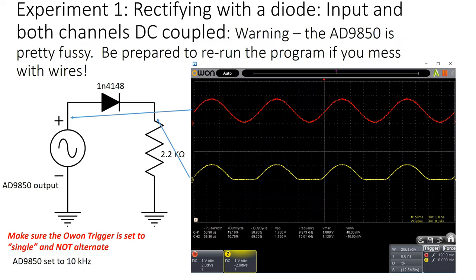So how do you measure the peak value of an AC waveform, that is an alternating sine wave waveform? Well, one way to do this is to use the diode you saw before when we looked at the characteristics of components, that a diode conducts in only one direction. Therefore, the voltage that will pass through a diode should correspond to only the positive voltage. And so we can use this as a starting point in finding a peak voltage.